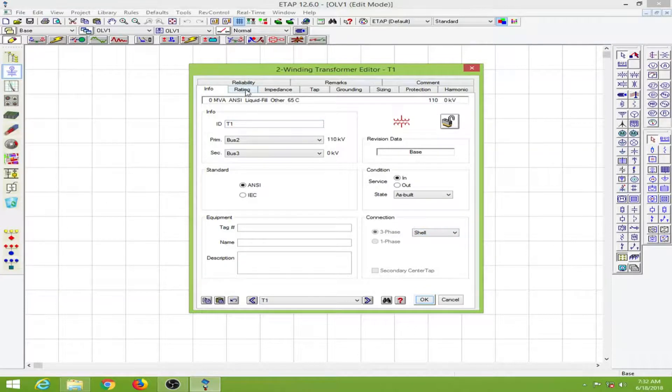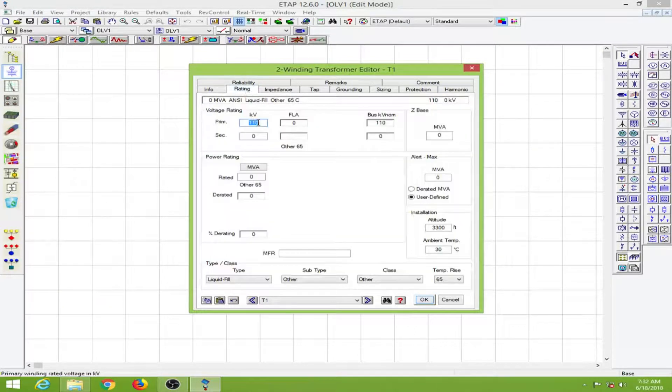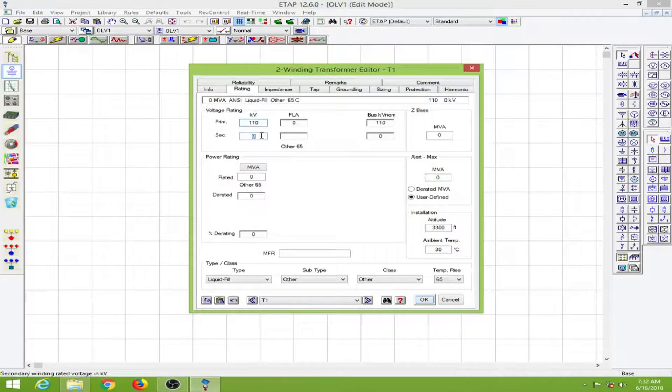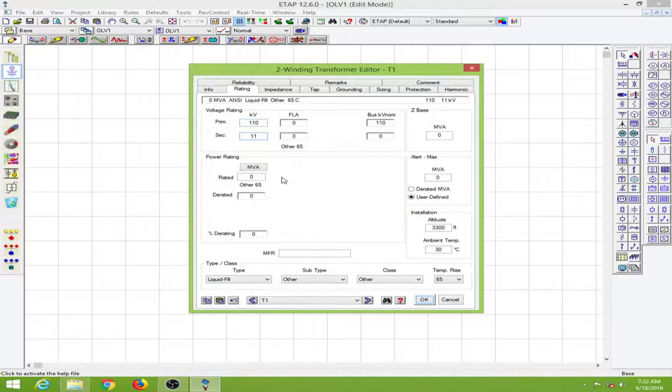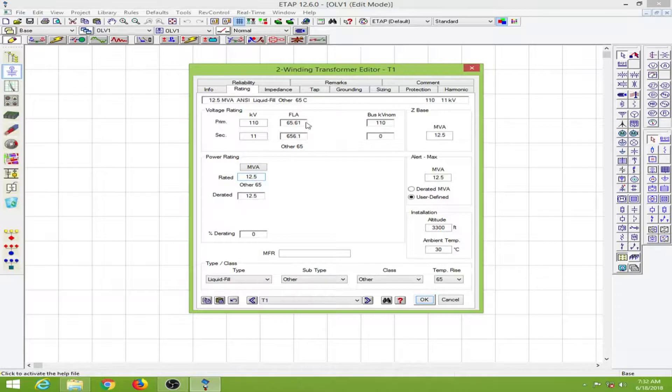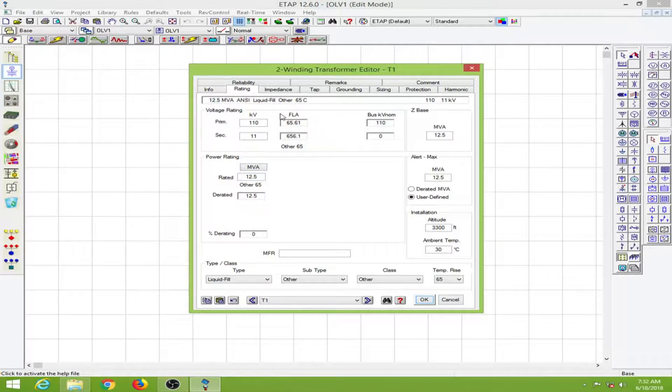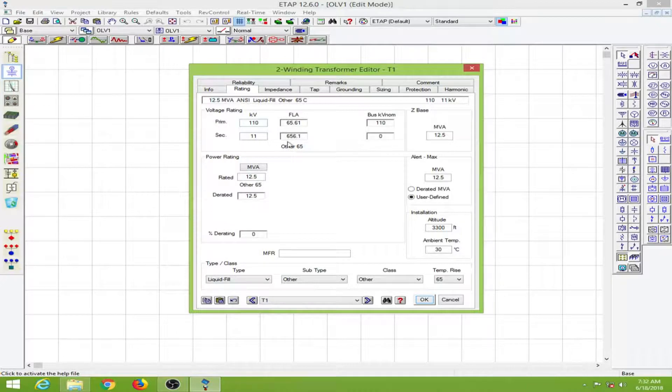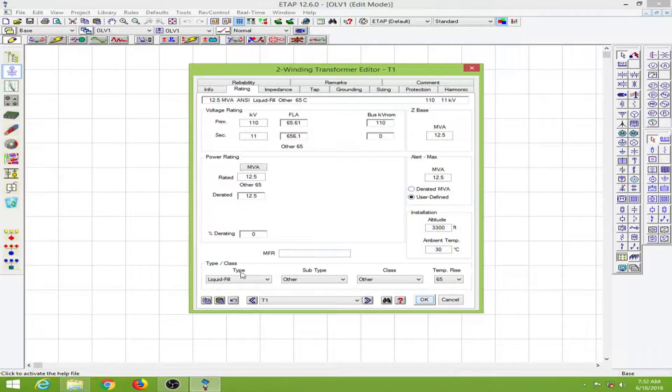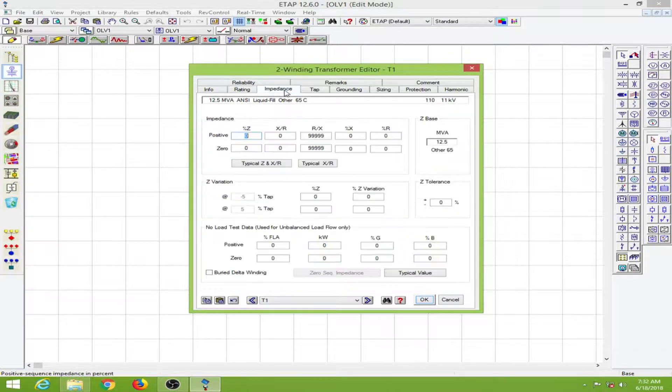Let's go to the rating page. I have the primary at 110 kV. I will make the secondary 11 kV. Then I will fill the power rating as 12.5 MVA. This automatically brings the full load current, about 65 amps for the primary and 656 for the secondary. Everything else I will keep the same.